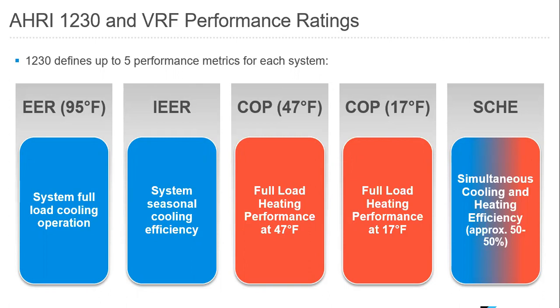Those metrics include EER at 95 degrees Fahrenheit, IEER, which is the system's seasonal cooling efficiency, and the COP at 47 degrees, which is the full load heating performance at 47 degrees. Then there's a second heating performance, the coefficient of performance at 17 degrees Fahrenheit, which is the full load heating performance at 17 degrees. And then several years ago, another key metric was defined, called SCHE, which is simultaneous cooling and heating efficiency. That describes the efficiency of the VRF system on a day when we might have simultaneous heating and cooling occurring in a building.